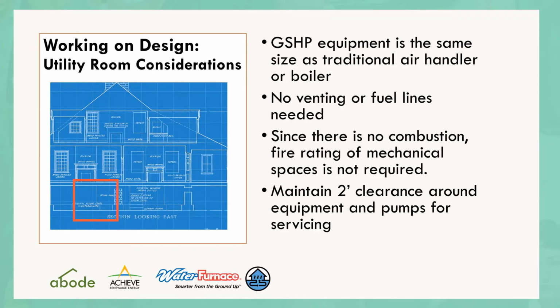Relative to the mechanical room, there are some advantages for ground source heat pump. The equipment's about the same size as conventional air handlers or furnaces and boilers, but we don't need any venting or fuel lines, so it can be central to the structure. It doesn't have to be on an outside wall. And since we have no combustion, there's not a requirement that that space have a particular rating for the wall and ceiling construction. We do need some space around the equipment for service. Typically 2 feet around the equipment is what we ask for, but that's the same as a conventional piece of equipment.